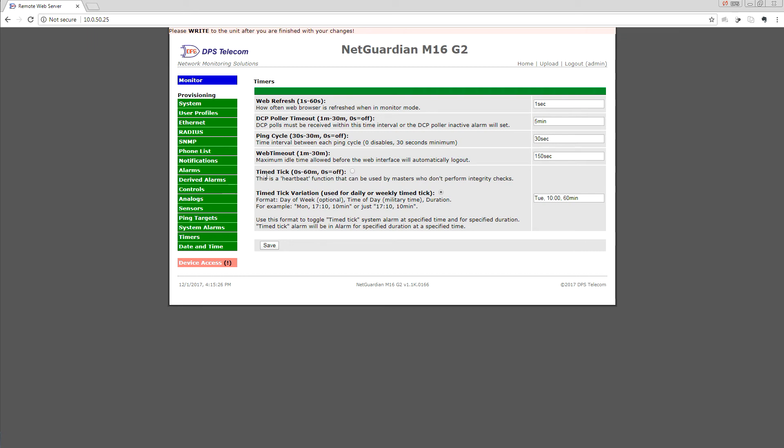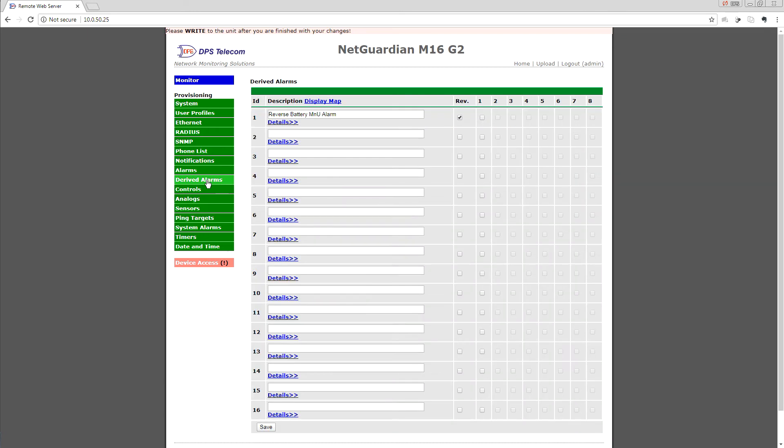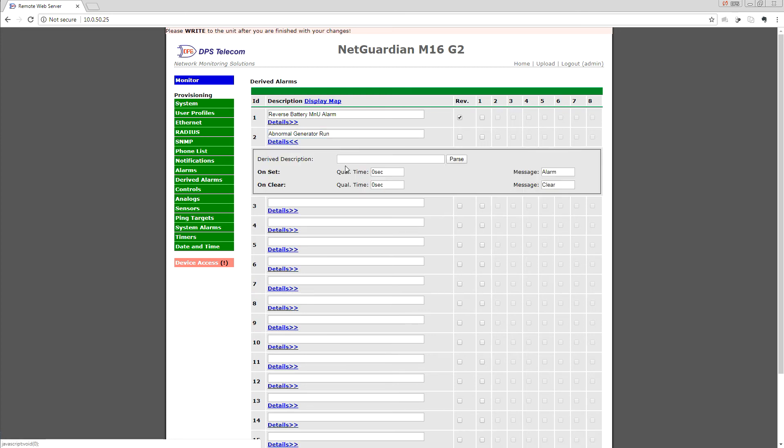Now that we have our two components, we head over to Derived Alarms. These are virtual or soft alarms that you program based on various input components. I already have one set up, so I'll use derived alarm point 2, and I can give it a name. We'll call it 'Abnormal Generator Run' because this is going to be our generator operating outside of its normal window. Then in the details, the derived description, this is a logical formula that explains to this derived alarm when it needs to be set and when it needs to be clear.